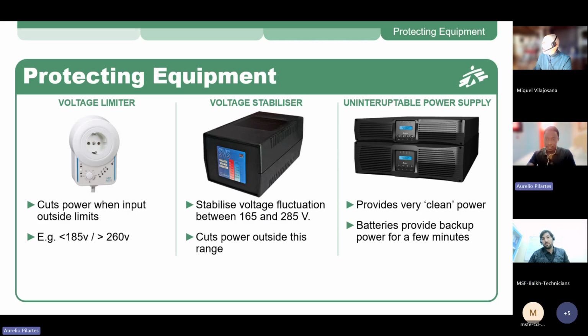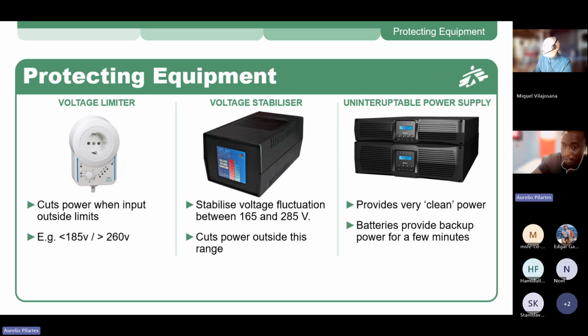Okay, thank you for this question, Shawad. As we were mentioning, the UPSs, and especially the Delta Amplon UPSs we use in our projects, already have the function of protecting your devices against voltage fluctuations. And the AVR you would put to protect the UPS cannot do this protection better than the UPS does. The UPS has a range within which it will always transform the voltage and give a better output voltage.